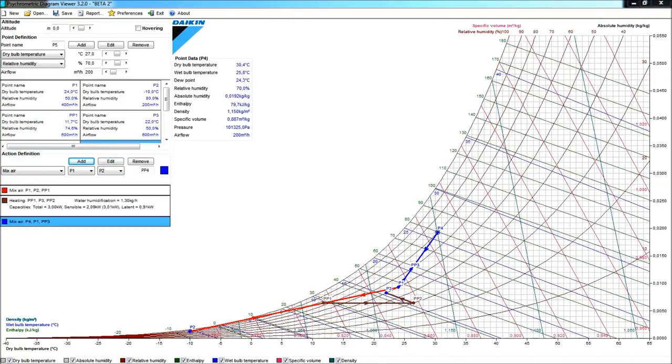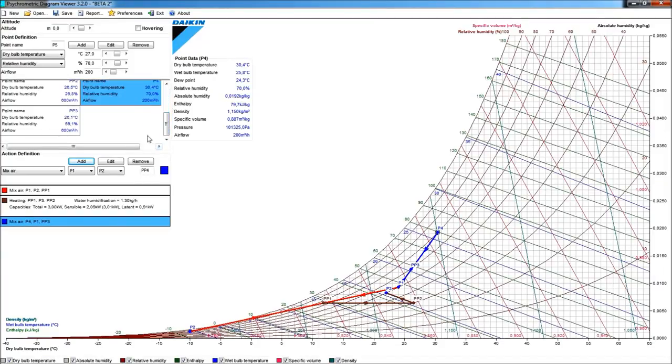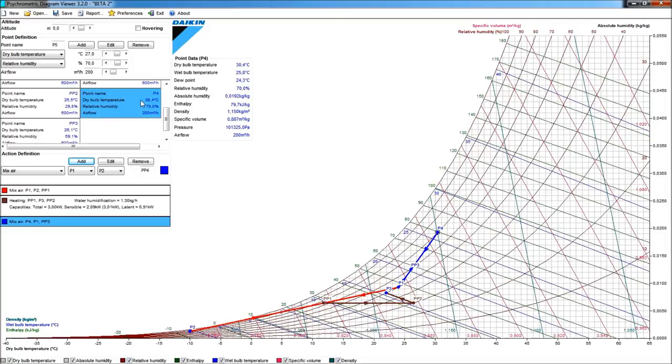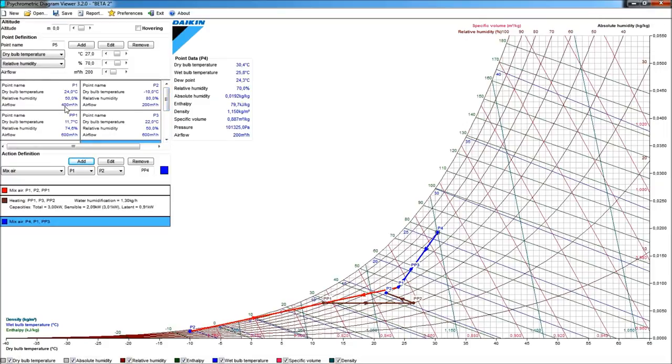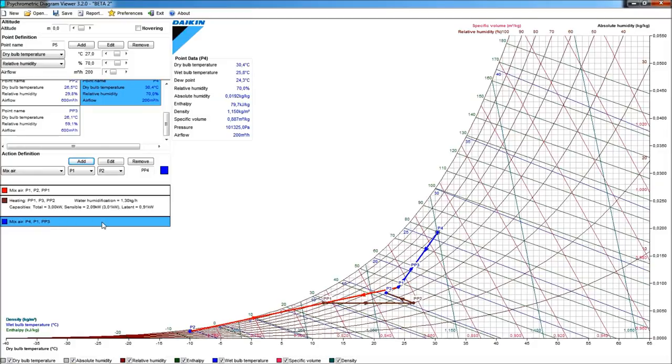Okay, I continue the exercise by adding a condition in summer, for instance, where I did specify the condition for the point P4, and by the way you see there is an elevator bar here now, that condition P4 was 30.4 degrees centigrade dry bulb and 70% relative humidity. Again, I would take about half the amount of air that I take away from the room in fresh air, so 200 cubic meters of fresh air, as opposed to the 400 that we had in point P1, the 400 cubic meters per hour. Okay, so this is my outside condition. Obviously, I can have an action mix there, where I end up actually in the point PP3.